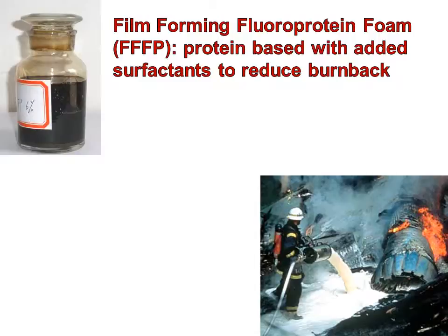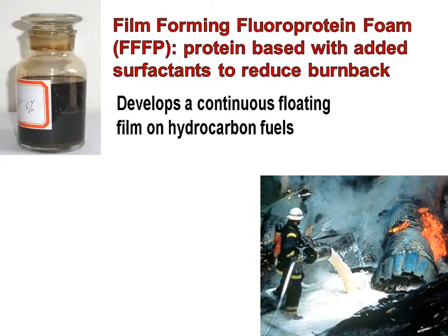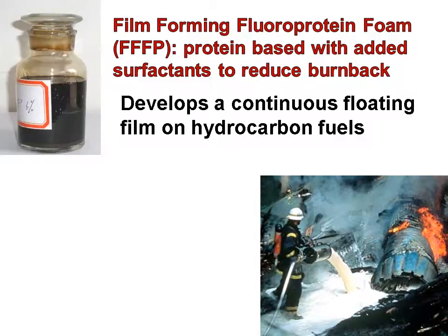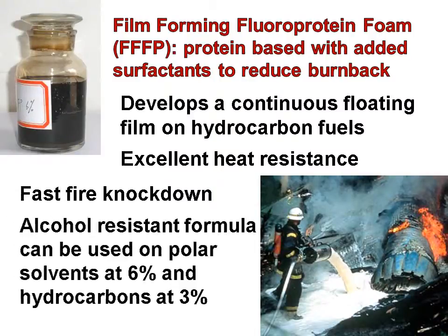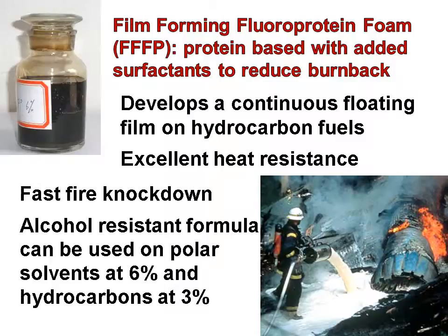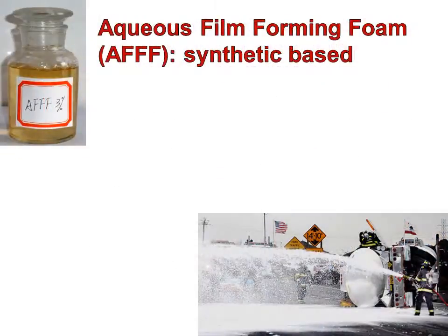Film forming fluoroprotein foam is a protein base with added surfactants to reduce burnback. Develops a continuous floating film on hydrocarbon fuels. Excellent heat resistance, and it's got a fast fire knockdown. Alcohol resistant foam can be used on polar solvents at 6% and hydrocarbons at 3%. Non-toxic and biodegradable after dilution.